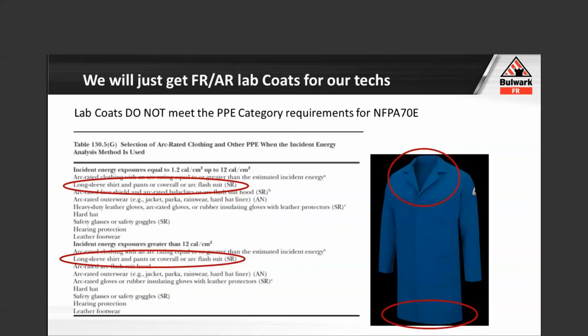They won't be displeased with me enforcing a flame-resistant, arc-rated clothing program, and I'll just have an inventory of quote-unquote lab coats that they can don to go do these energized tasks. But at no place anywhere in NFPA 70E, under any of the selection methods for flame resistant and arc rated clothing, are you allowed, or does it even mention that you can utilize a lab coat.